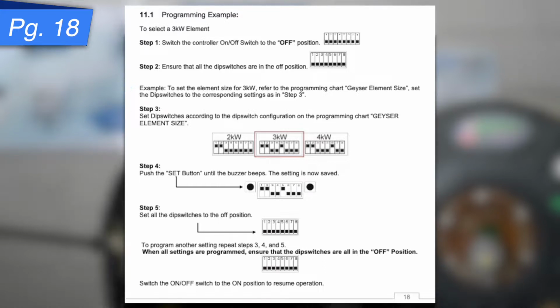For a 2, 3, and 4 kilowatt, this is now step 3 on page 18. So you would move the dip switches to the correct element size. Then step 4, you would push one of those buttons until the buzzer beeps. When it beeps, it is saved. Once you've completed that and it's saved, you can move all the dip switches down as in number 5. Don't push anything, it's now in a safe position.